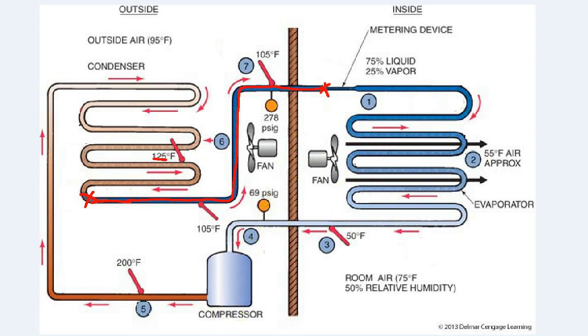Now, it is important to have subcooling in our system because if we don't, each one of these bends that we have in the condensing coil and going into the house, any 90 degree bend, 45 degree bend, sometimes the lines get a little kinked or mushed as they go through the outside wall or pulled through the chase. Anytime we have anything like that, it drops the pressure just a little bit.